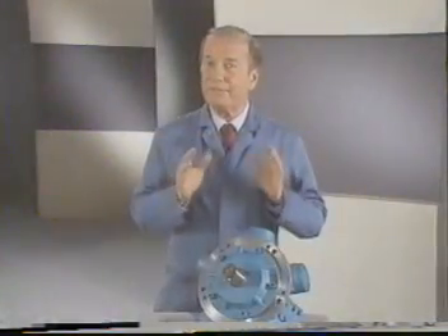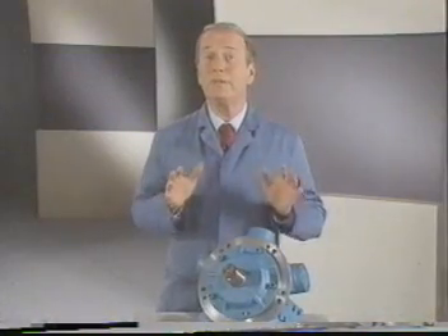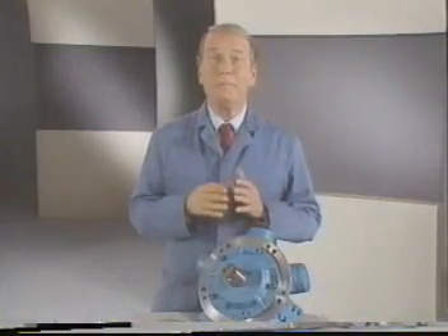A relief valve doesn't have to be anything more than a ball held on a seat by a spring. You just tighten up on the spring until it's harder to push the ball off its seat than it is to drive the motor with its normal load. Overloading the motor would cause the ball to lift off its seat and divert the pump flow back to the tank, permitting the pump and electric motor to run even though the hydraulic motor is stalled.